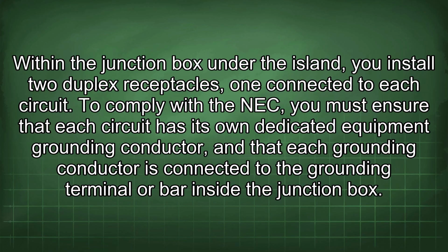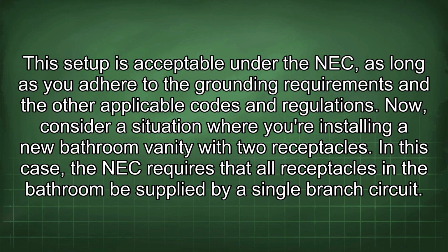To comply with the NEC, you must ensure that each circuit has its own dedicated equipment grounding conductor, and that each grounding conductor is connected to the grounding terminal or bar inside the junction box. This setup is acceptable under the NEC, as long as you adhere to the grounding requirements and the other applicable codes and regulations. Now consider a situation where you're installing a new bathroom vanity with 2 receptacles.